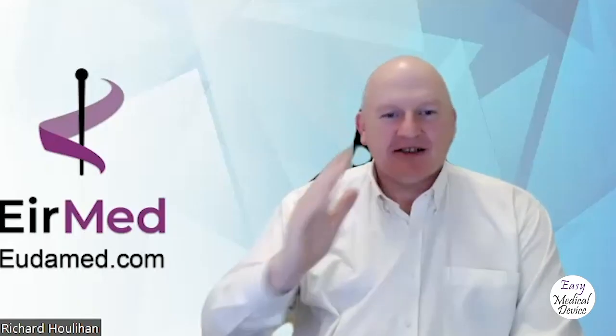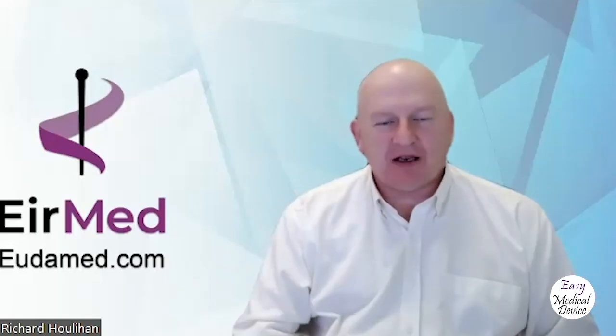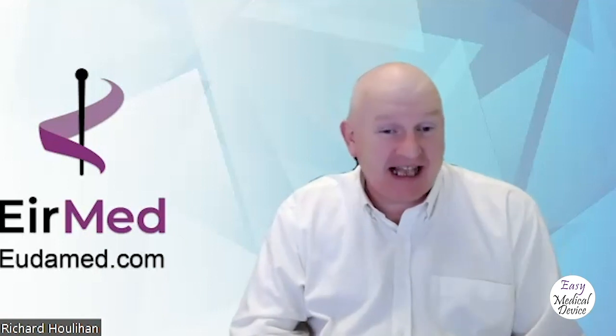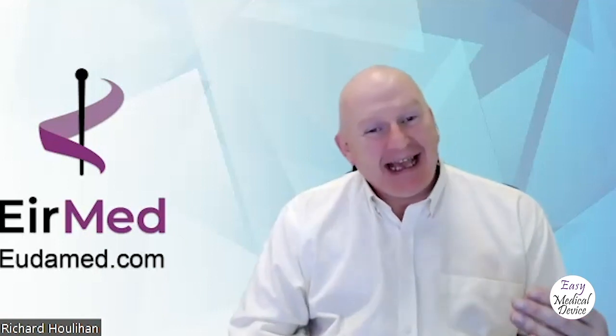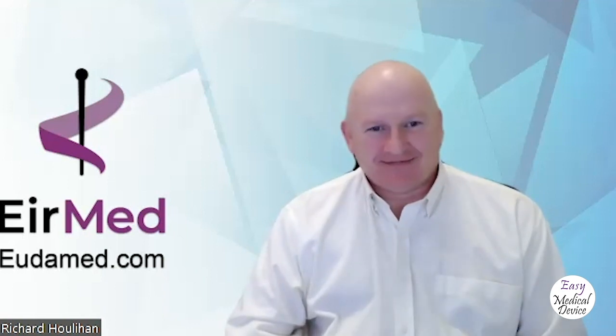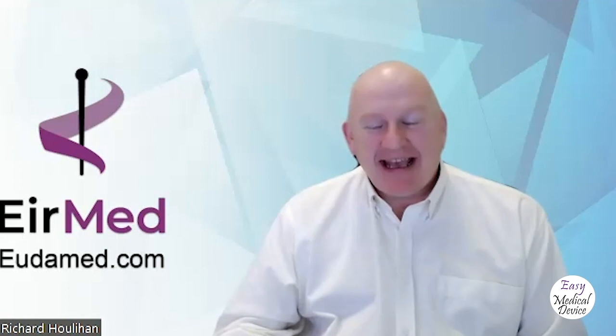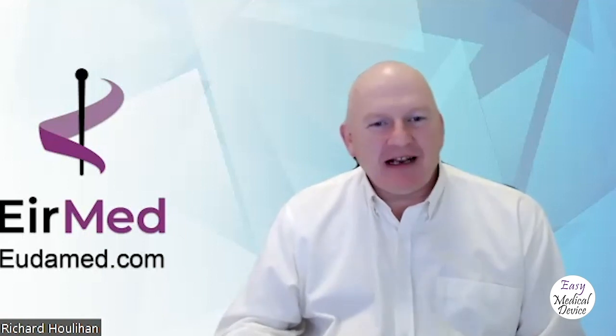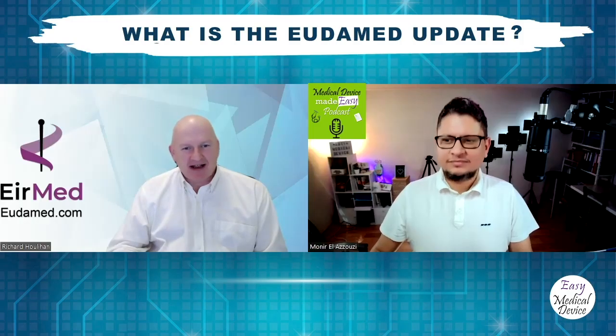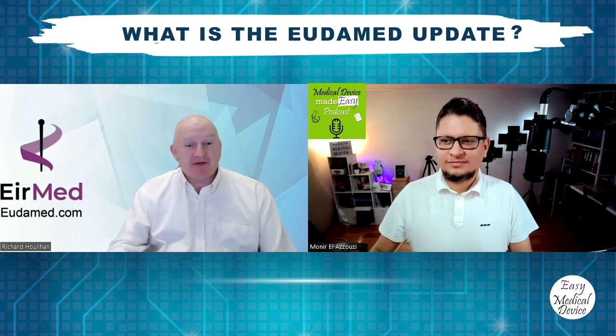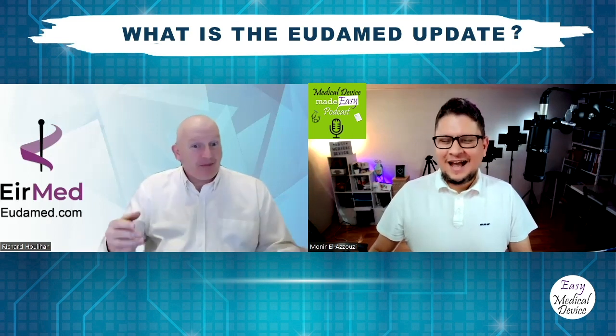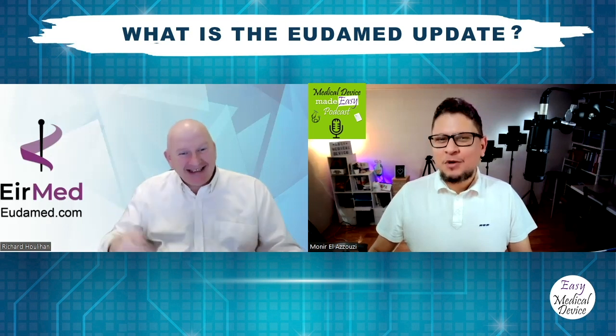However, because EUDAMED is so far away from being fully functional, and it in itself is not currently mandatory, but, there's a big but, it takes very little time to register for your SRN. If you want to pay someone to do it for you, hey, we offer the service. But I help companies with that. And yeah, it takes 20 minutes, as long as you have the documents signed and ready to be uploaded. 20 minutes, it's done, it's finished.